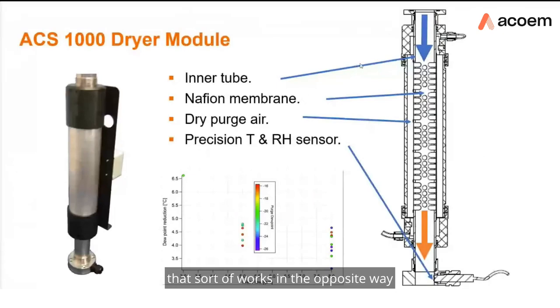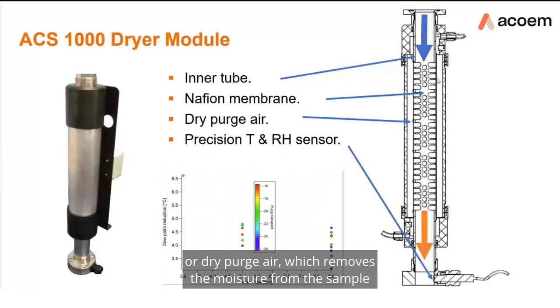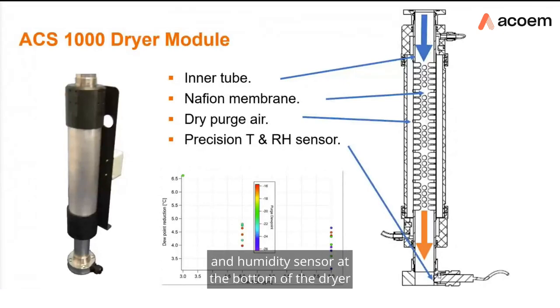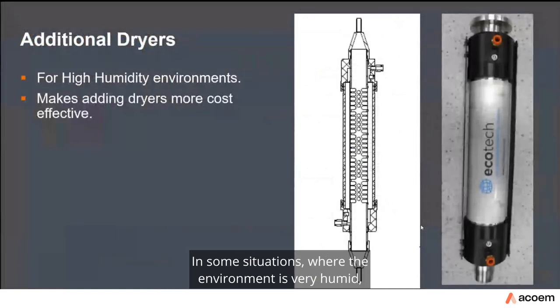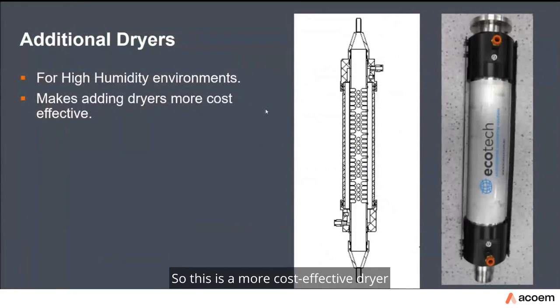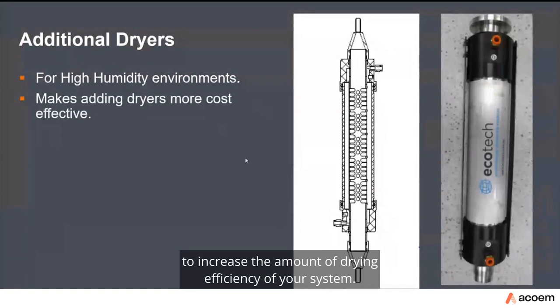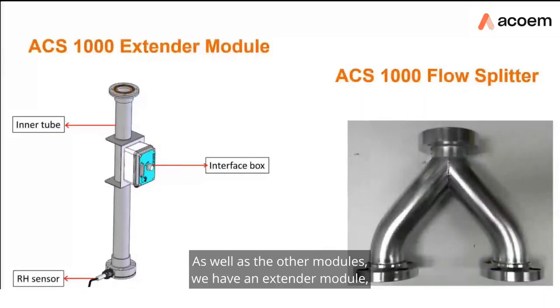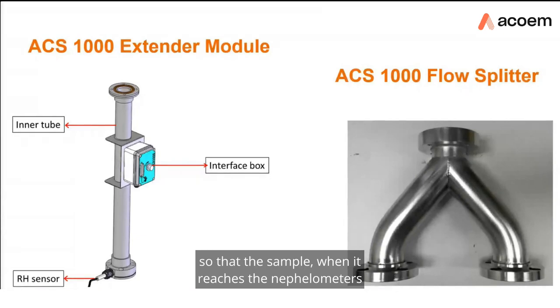The dryer module works in the opposite way with a similar size to the humidifier. The inner tube is covered with a Nafion membrane and on the outside is a dry purge air flow which removes moisture from the sample. A precision temperature and humidity sensor at the bottom of the dryer measures the outlet humidity. In very humid environments, additional cost-effective dryers can be placed in series with the ACS dryers to increase drying efficiency. There is also an extender module — a solid tube — that extends the path length for both channels, ensuring the wet and dry samples reach the nephelometers at the same time so enhancement factor calculations use data from the same time frame.